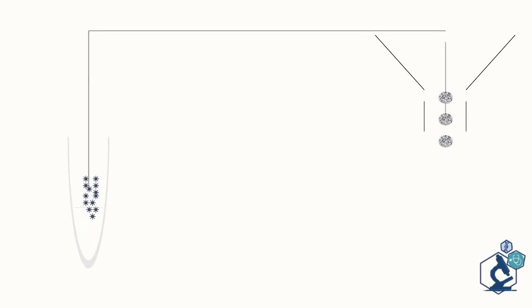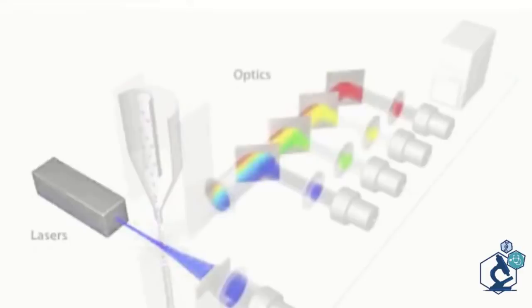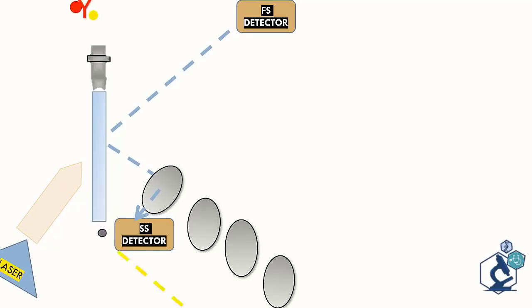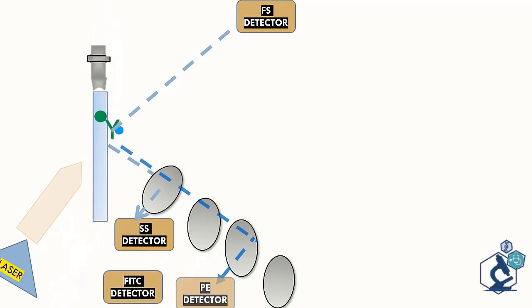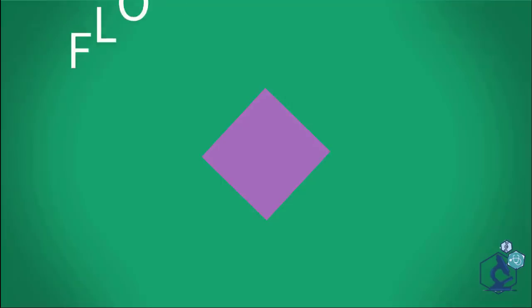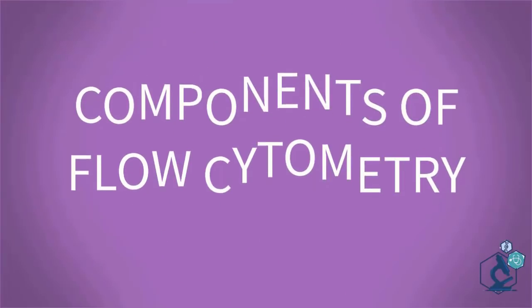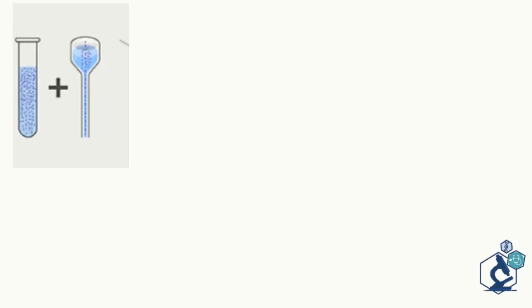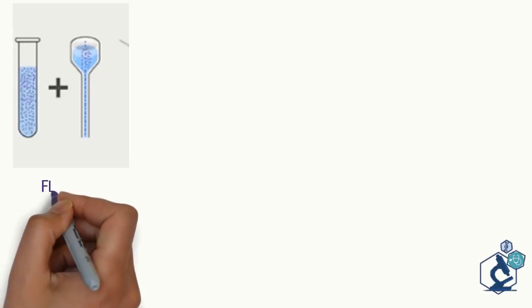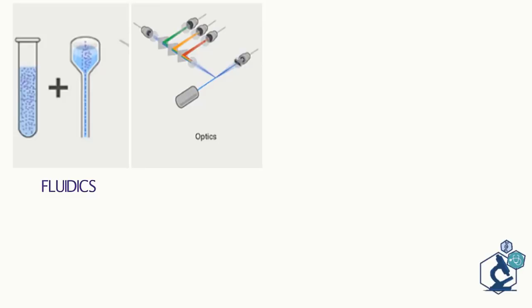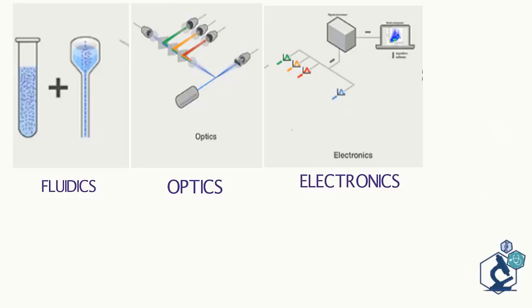An overview of flow cytometry methods. Cells in suspension flow in a single file past a focused laser where they scatter light and emit fluorescence. Emitted fluorescent light is then filtered by lenses and collected on receptors which convert them to digitalized values in the form of plots. Flow cytometer contains different components including fluidics that move the cell in sample into the flow cytometer, optics which emit and gather the light with the help of detectors and a computer system to acquire the data in the form that can be analyzed by a researcher.